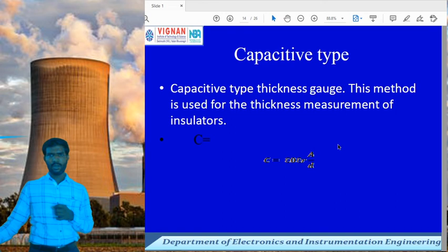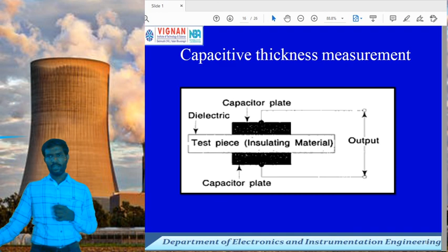One more important method is the capacitive type thickness gauge. This capacitive method uses the formula C = ε0 εr A / d, where the relative permittivity depends on the dielectric constant, and two parallel plates are used in this arrangement. Between the two parallel plates, we place a test piece which acts as an insulating material. Based on the thickness of the insulating material, the output across the two parallel plates changes. So these dimensions are measured in the paper and pulp industry by the capacitive method.